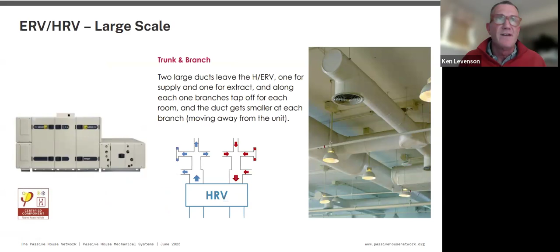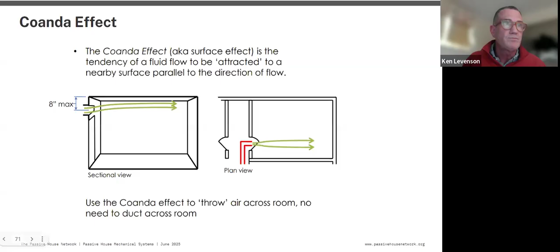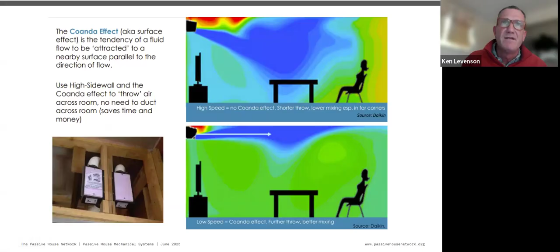One of those aspects is pulling the systems back to the core, which is very attractive in terms of simplifying things and lowering costs. But we still want to make sure the air gets everywhere with the ventilation. So typically utilizing something of the Coanda effect, where we're bringing that air in close enough to the ceiling surface so it's actually using that surface to throw the air across the room. So it's the same low flow, and to be able to do it at a low speed. The ventilation rates are typically quite low, 20 CFM. It's not air conditioning. And as it goes out, it can then kick the air across the room.